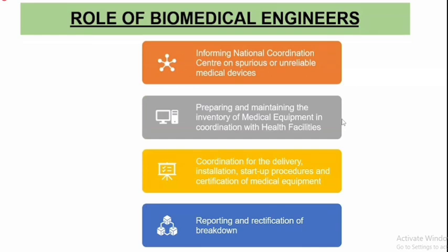Then what are the basic roles of the biomedical engineer in a healthcare facility setup? In terms of the materiovigilance program of India, the most important role a biomedical engineer can perform is informing the National Coordinating Center or their monitoring centers on any kind of adverse events or any unreliable medical device events that are occurring at their healthcare facility level.